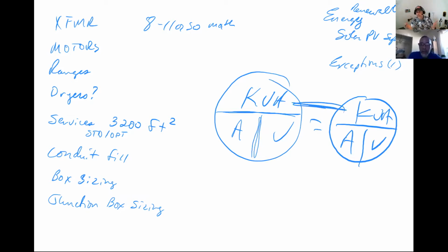The constant between the two of them is that kVA will be the same on both sides. Now if the bottom two values relate to each other in a different manner, like one goes up and one goes down, then to get that kVA on the other winding to stay the same, you have to have the opposite movement of those other two items on the other side. But the kVA is the kVA for both the primary and the secondary. That's the beauty of this mental picture, because it keeps it nice and simple.